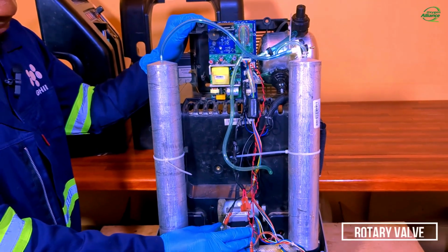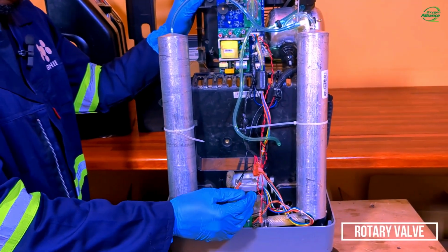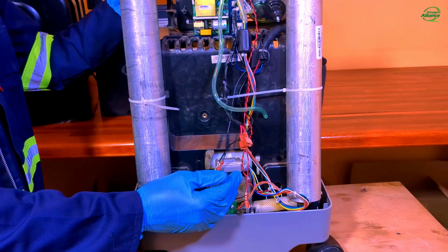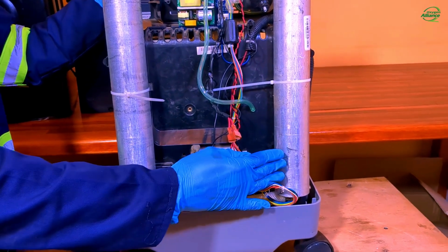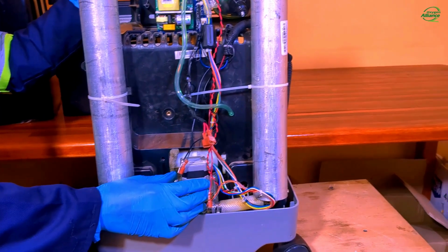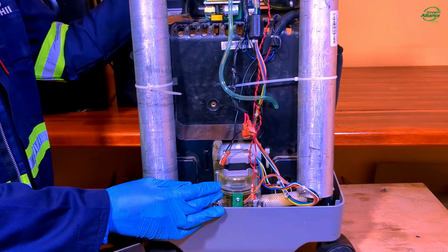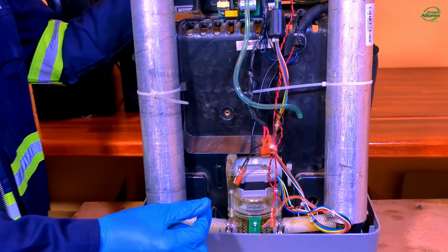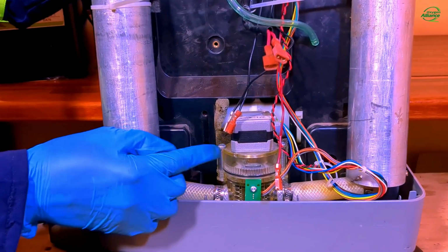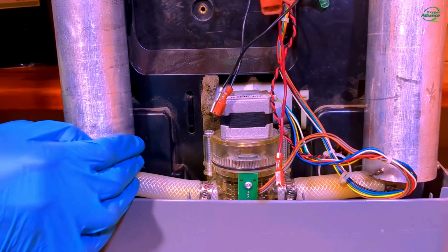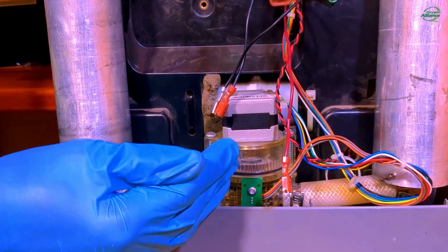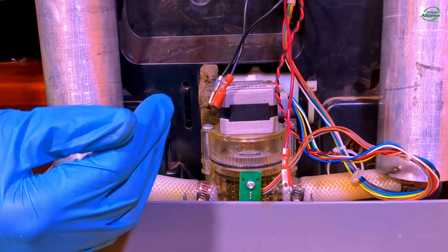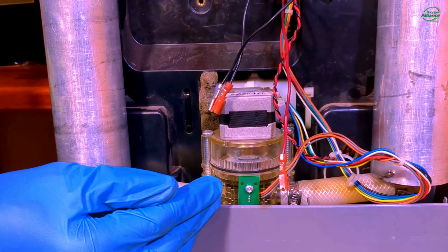So the rotary valve controls the direction of air being fed into either of the sieve beds. The rotary valve has a stepper motor which is connected to a disc that has circular holes. So as the stepper motor is rotating, it controls the opening and closing, thereby controlling the passing of air to the sieve beds.